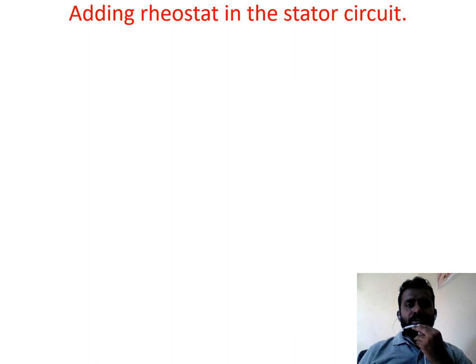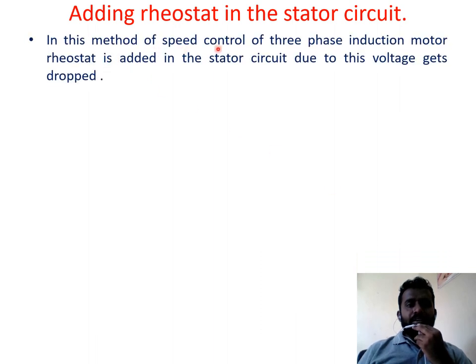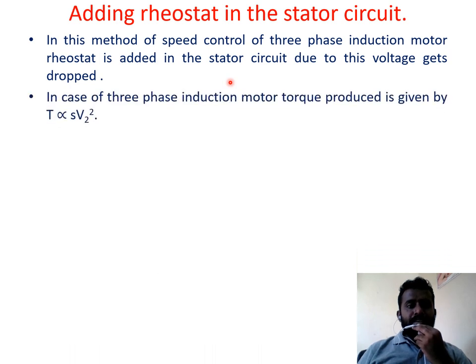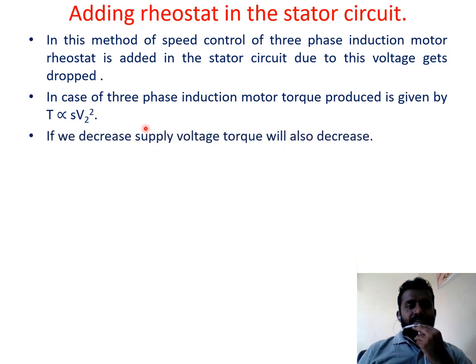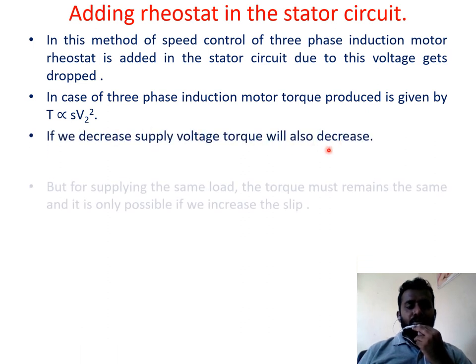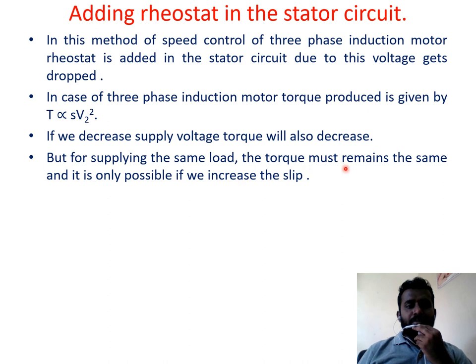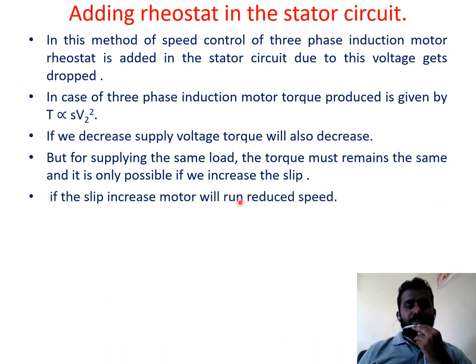Adding a rheostat in the stator circuit: a rheostat, which is a variable resistor, is added in the stator circuit. Due to this, voltage drops across the resistance. If resistance is increased, voltage automatically decreases. Since T is proportional to V², decreasing supply voltage decreases torque. But for supplying the same load, torque must remain the same, so slip increases and motor speed decreases.